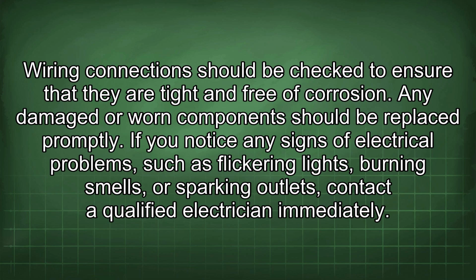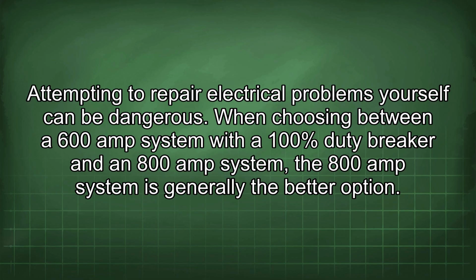If you notice any signs of electrical problems, such as flickering lights, burning smells, or sparking outlets, contact a qualified electrician immediately. Attempting to repair electrical problems yourself can be dangerous. When choosing between a 600 amp system with a 100% duty breaker and an 800 amp system, the 800 amp system is generally the better option.